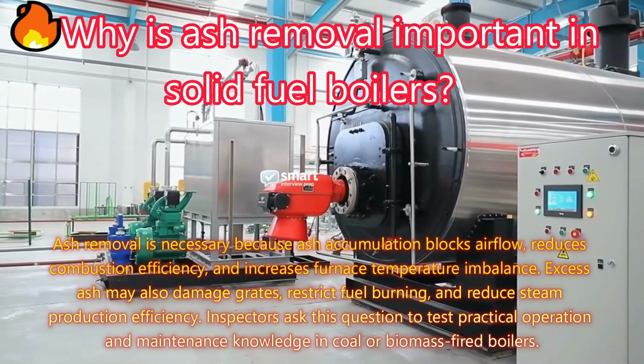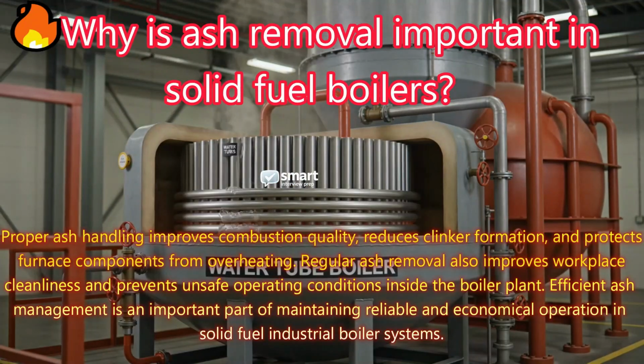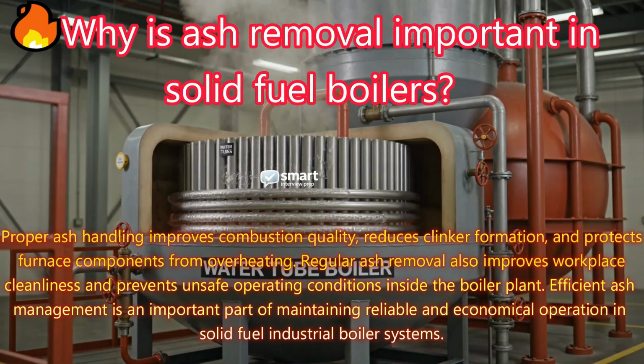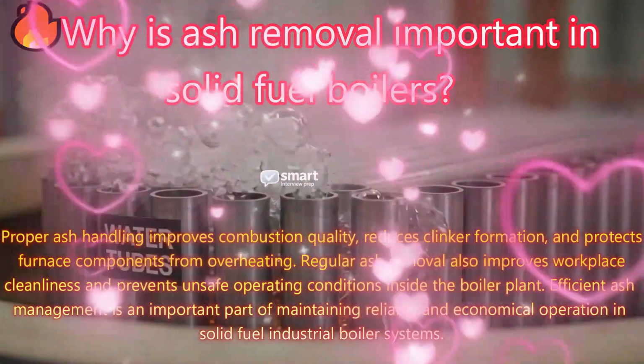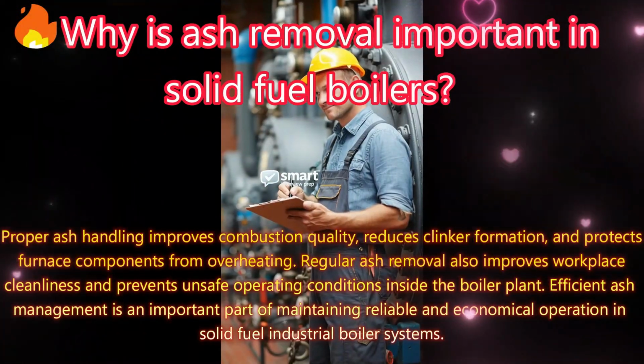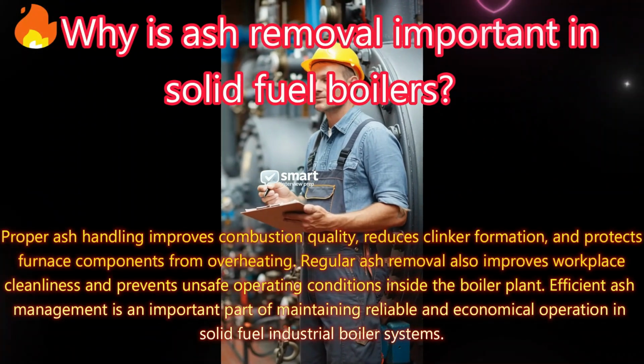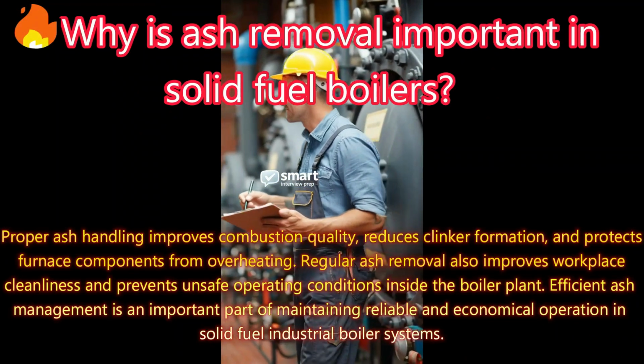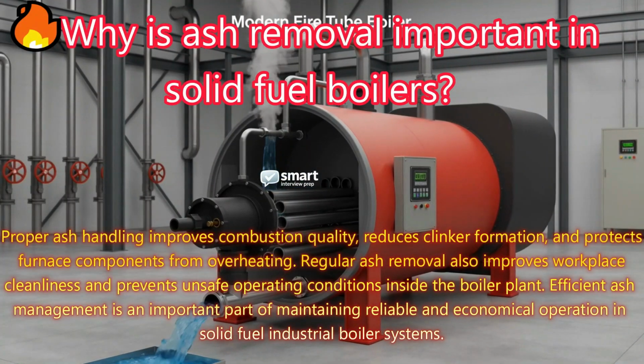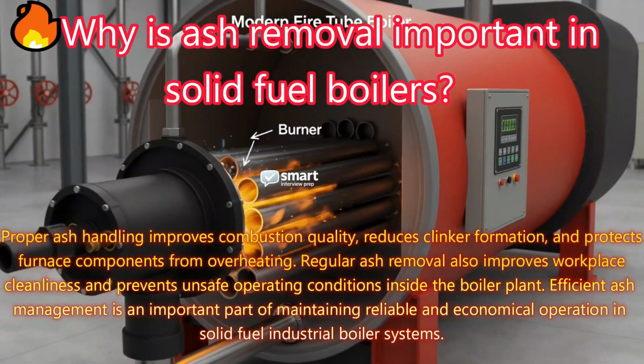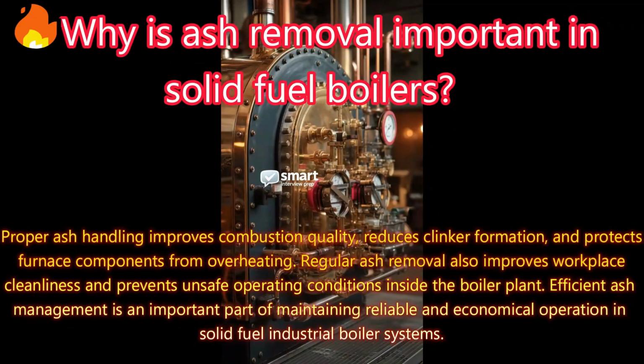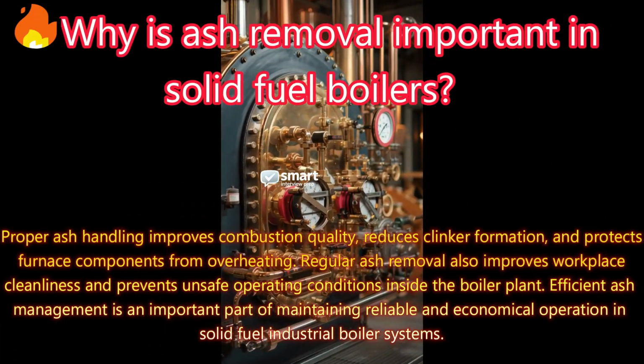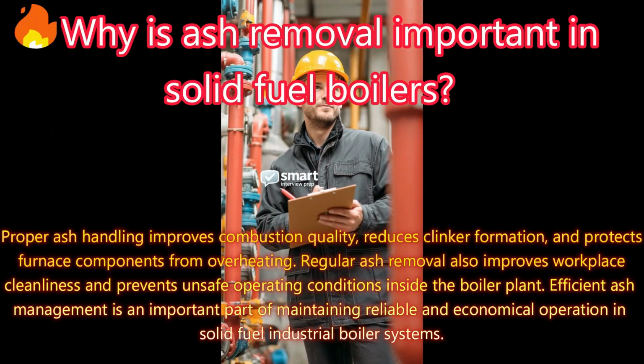knowledge in coal or biomass-fired boilers. Proper ash handling improves combustion quality, reduces clinker formation, and protects furnace components from overheating. Regular ash removal also improves workplace cleanliness and prevents unsafe operating conditions inside the boiler plant. Efficient ash management is an important part of maintaining reliable and economical operation in solid fuel industrial boiler systems.